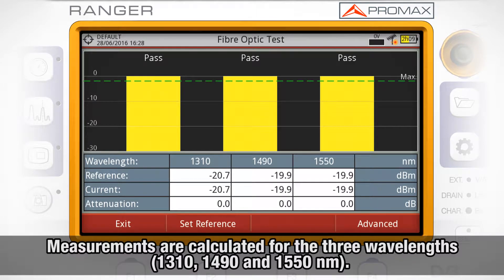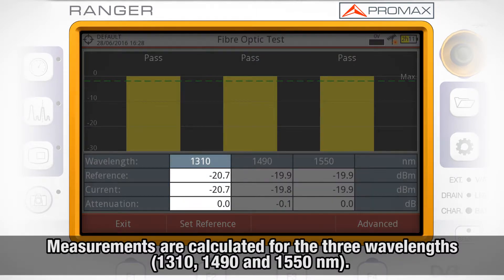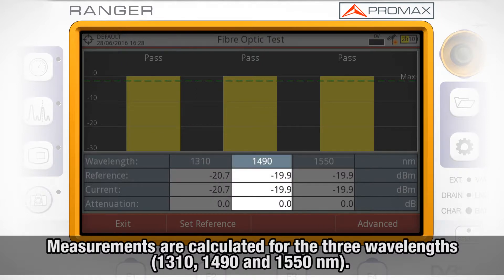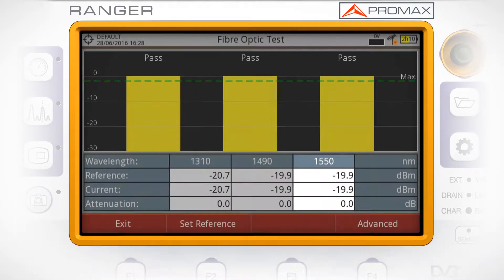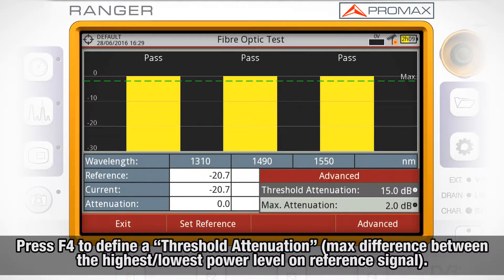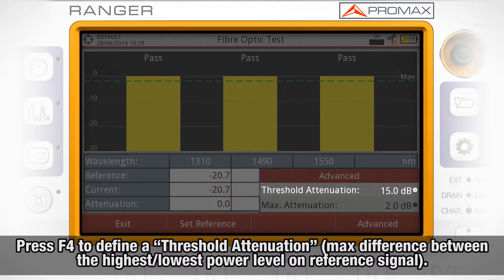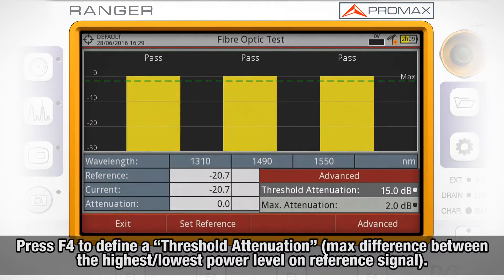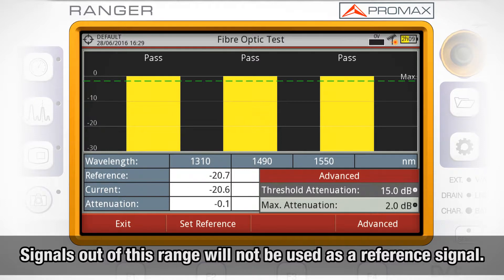All these measurements are calculated for three wavelengths: 1310, 1490, and 1550 nanometers. By pressing F4, you can define the threshold attenuation, which is the maximum difference that can exist between the reference signal with the highest power level and the reference signal with the lowest power level. Any signal out of this range will be deleted and not used as a reference signal during the measurement process.